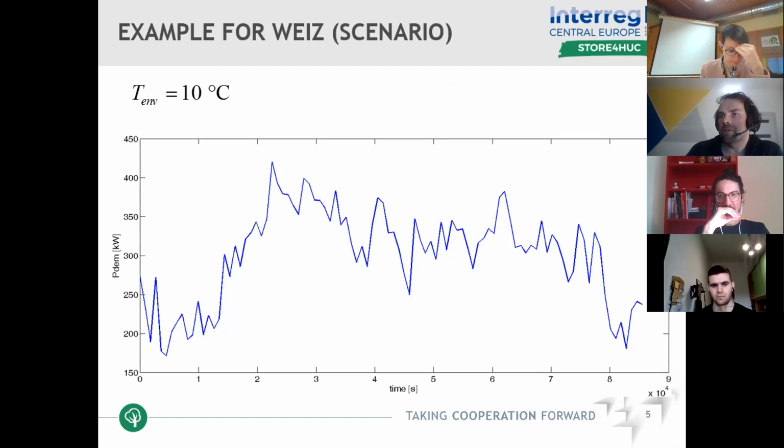And you can then even see whether you need to change something on your timers in your simple automation system regarding on and off times of your heat source to gain on the system operation efficiency. So it's not that it is only possible to be used for day ahead advising, but it can be also used to analyze the operation of your site and to see at the end, are you operating your heat sources efficiently or not? Is there a place for improvement?